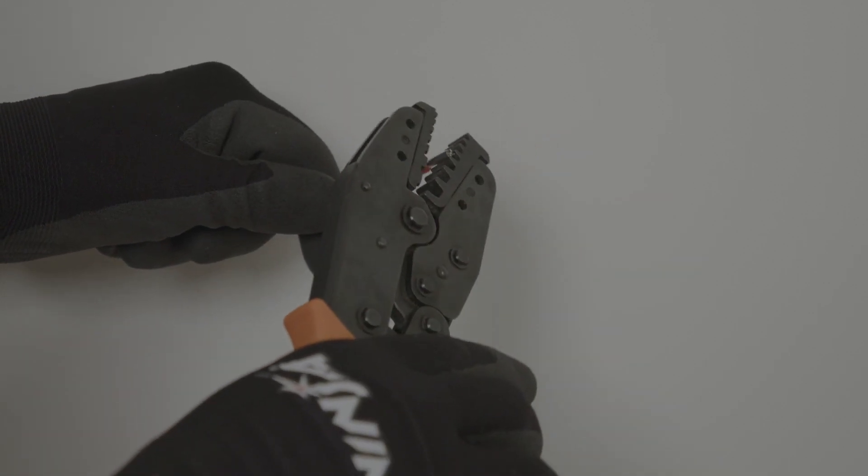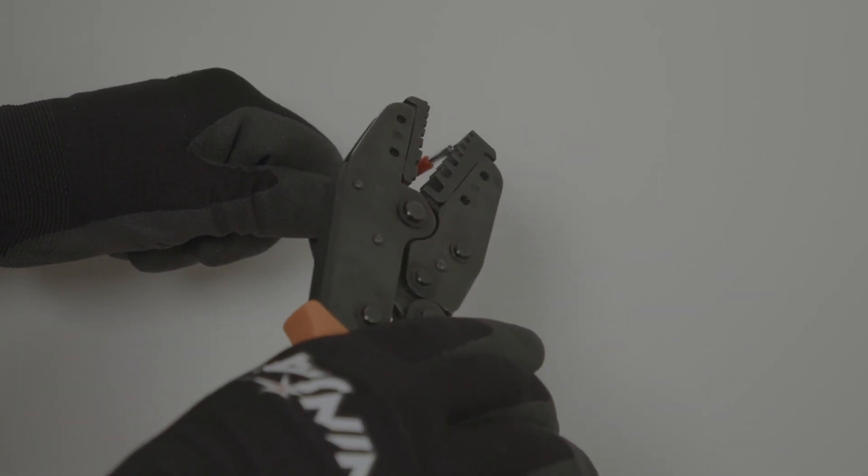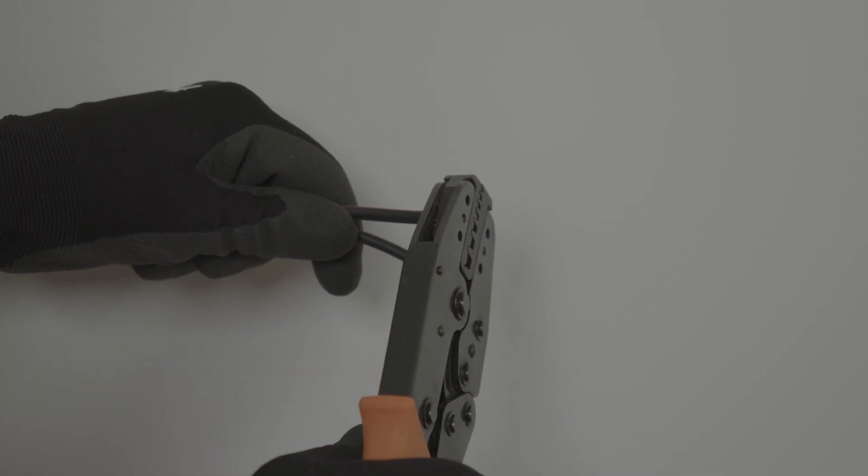For the DC, ensure that boot lace ferrules are always used to ensure good quality connection. If two into one connections are being used, from the battery and PV together, use a two into one boot lace ferrule.